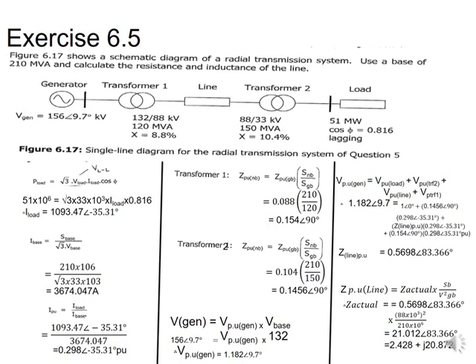With Z line per unit known, we use the relationship Z actual equals Z per unit times V squared over S, where the line voltage is 88 kV and S is 210 MVA. This gives Z actual equal to 21.012 at 83.36 degrees. Since they want resistance and inductance, we convert to rectangular form: resistance of 2.428 ohms and inductance component j20.872 ohms.